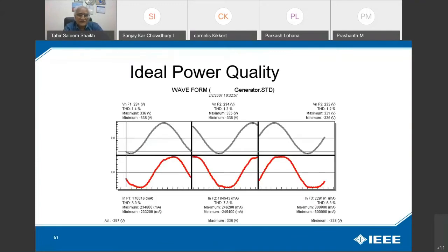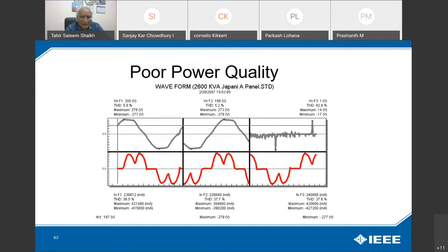If you come to an ideal power quality, this is a picture taken by our spectrometer. The above is the voltage and the lower is the line current, and the THD level varies 1.4, 1.3 and 1.2, and 6.9, 7.3 and 6.8. So this is ideal, and this is a defective one operating at the VFD. You can see over here the voltage distortion is not much, but the current harmonics is 36.5, 37.7. And on the third phase there is some problem in the connection, giving 37.6.